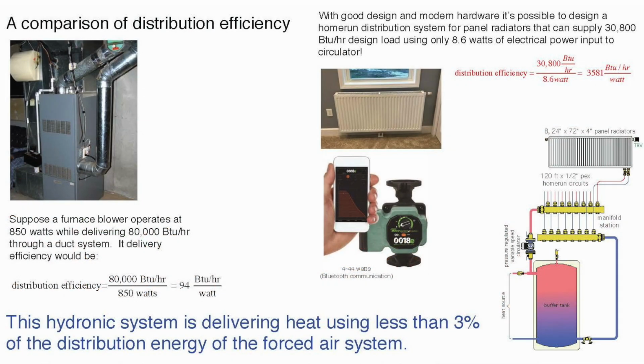So, let me jump over. Here's a furnace. It's delivering 80,000 BTUs per hour, and if you look up the power requirement of the blower, and I'll confess, this is a standard blower, not an ECM motor on the blower, it's 850 watts. So if we put the numbers in there and we divide, we get 94 BTUs per hour being delivered per watt of input to run that blower in that furnace.